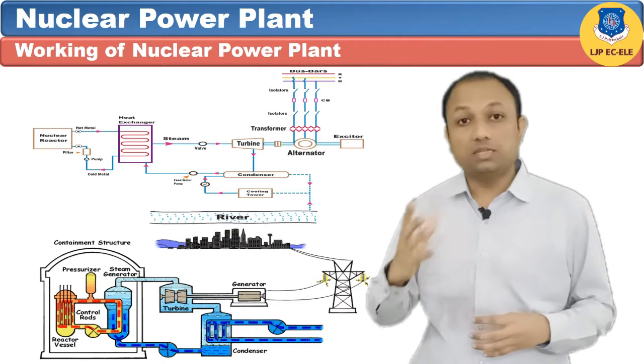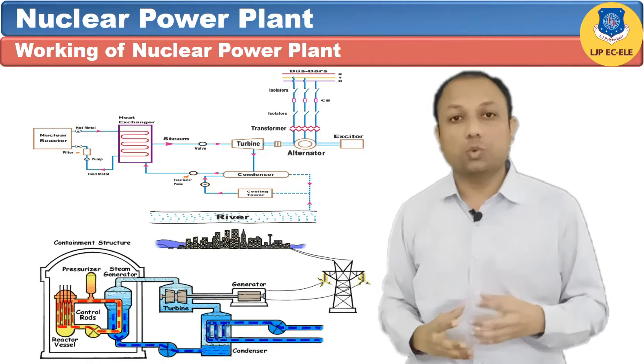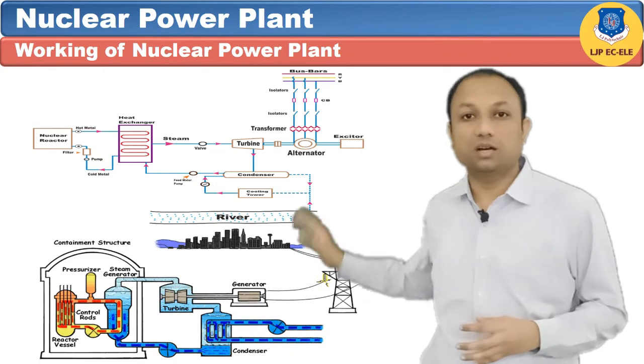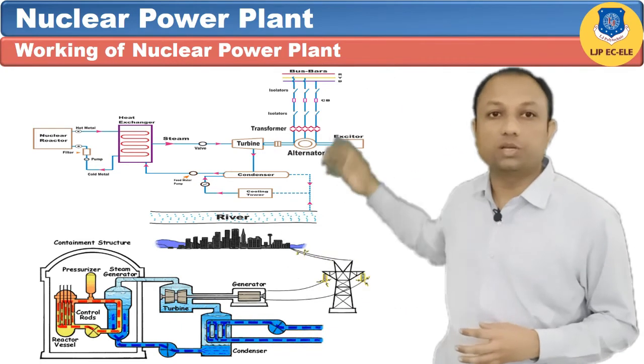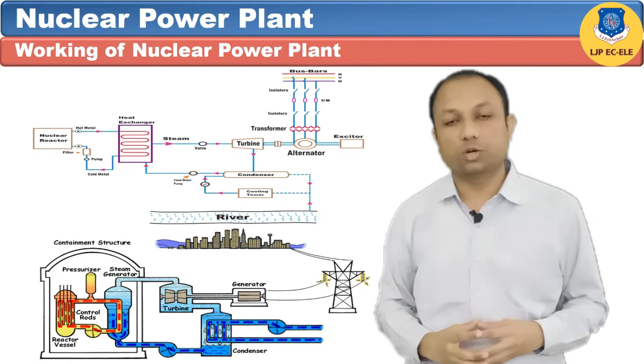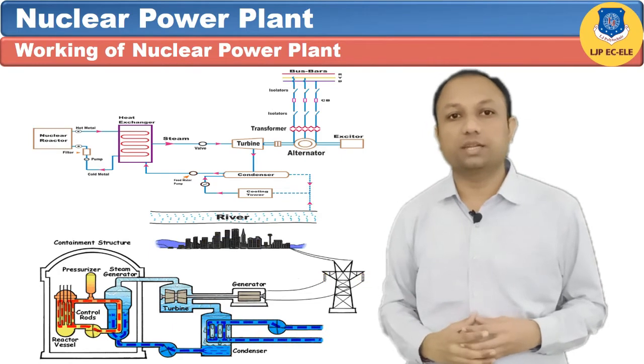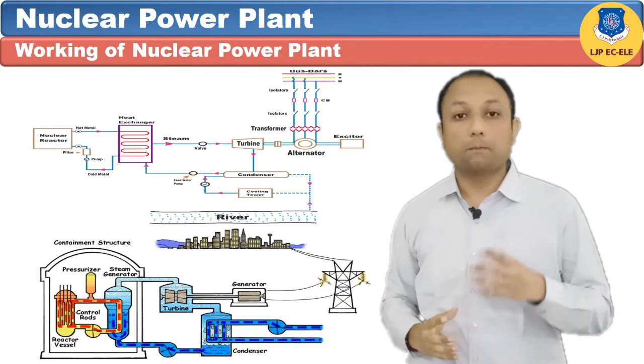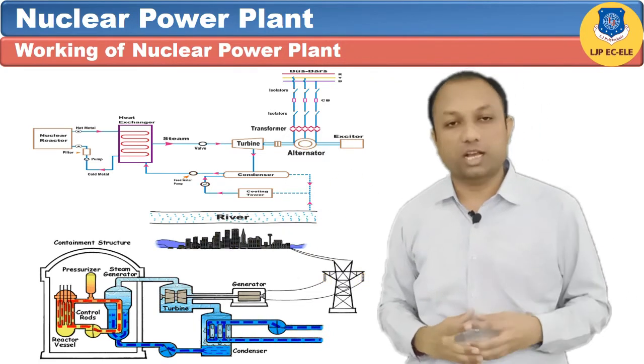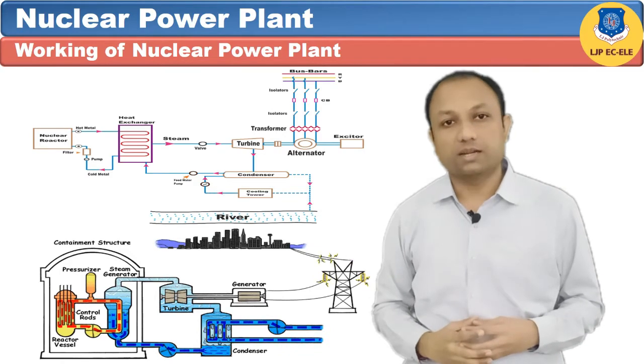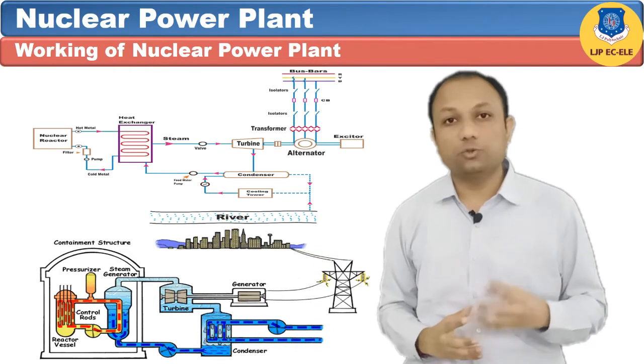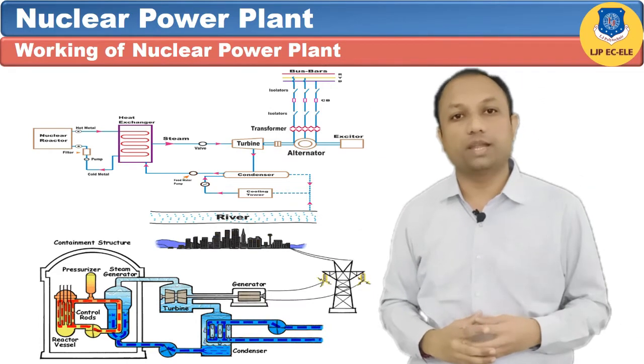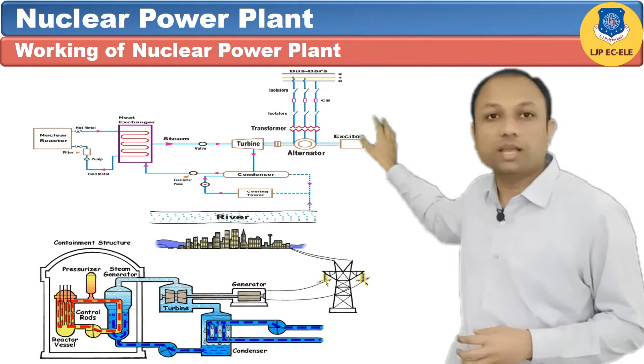The alternator, coupled to the turbine, converts mechanical energy into electrical energy. The voltage generated by the alternator is stepped up to the required value by a step-up transformer, and the transformer is connected to the bus bar through isolators and circuit breakers. Power is transmitted by transmission lines connected to the bus bars. An exciter coupled to the alternator generates DC supply necessary for the field winding of the alternator.